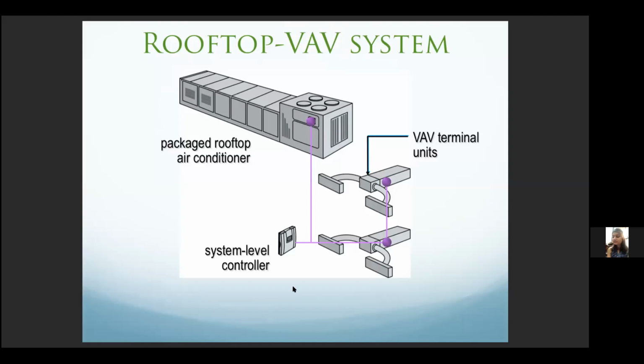So system level controllers come into place at that point, where they can understand how the VAV is operating. Is the VAV getting enough air? Is the VAV starving? Is the space satisfied? And if the VAV is starving, for example, it may ask the supply fan to ramp up speed so that the last VAV down the duct, whose room temperature is not being satisfied, can be helped.